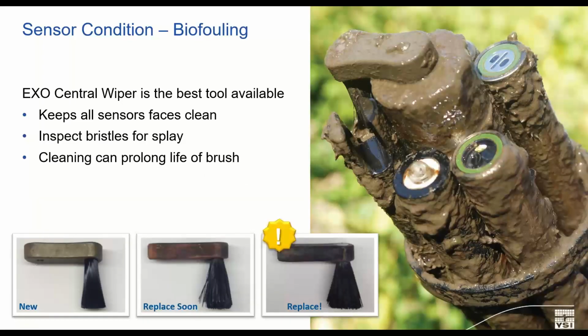So we talked a little bit about the sensors that are most common to both EXO and ProDSS, but for those of you that spend most of your time with long-term deployments, one of your biggest allies against biofouling and other buildup on the sensor faces during sampling is the central wiper assembly. It is crucial that you inspect the condition of the wiper block or brush assembly and the wiper itself prior to a new sampling season and after each deployment.